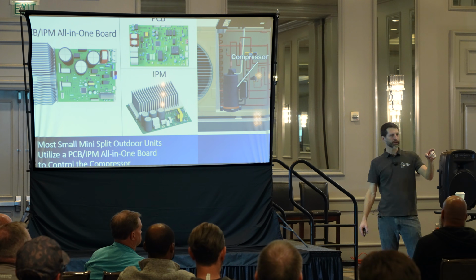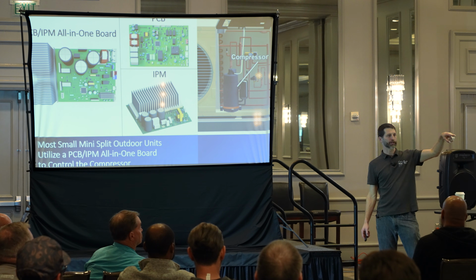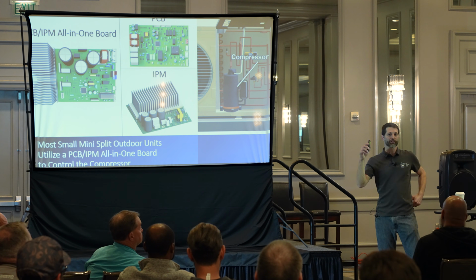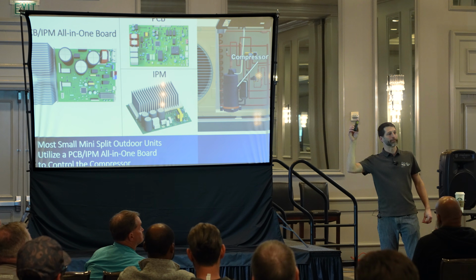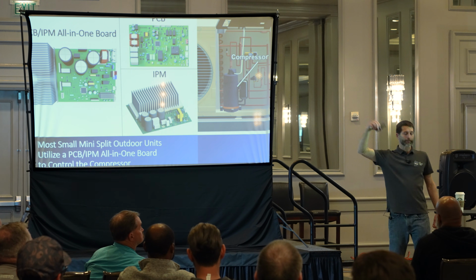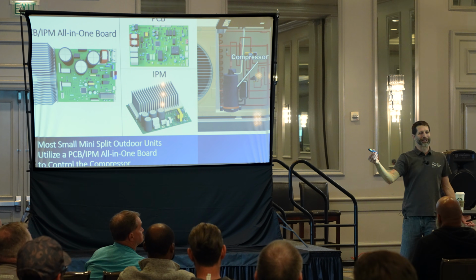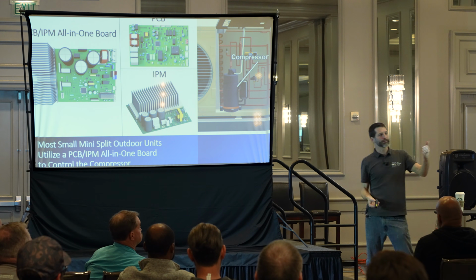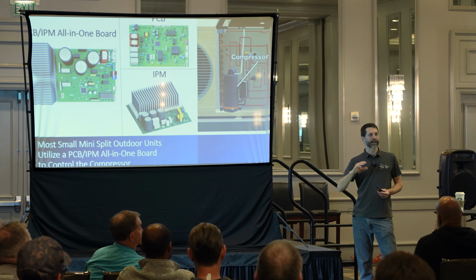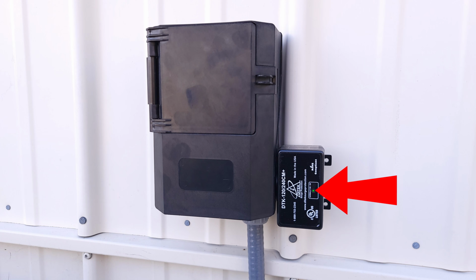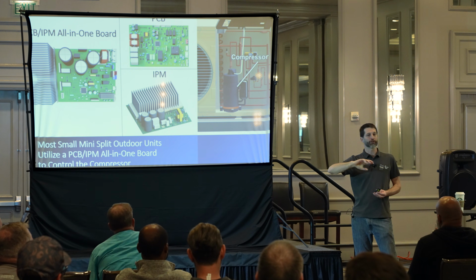They would not warranty the circuit board if it did not have surge protection. Yes, absolutely, surge protection is mandatory. But then you're saying, why don't they just put that in the outdoor unit? The reason is surge protection is not infinite. You have an LED that needs to be exposed to tell you when the surge protector no longer can protect the system and needs to be replaced.